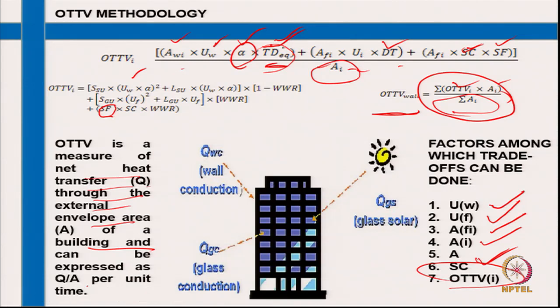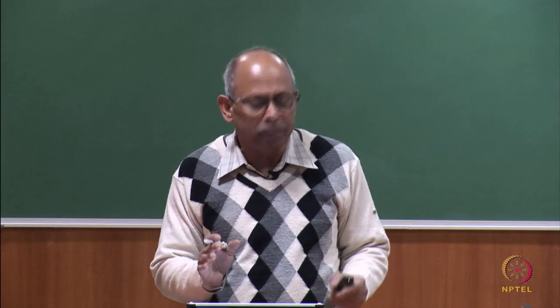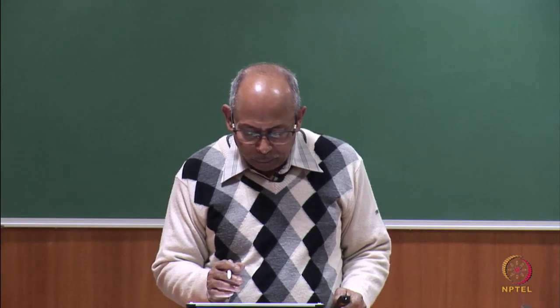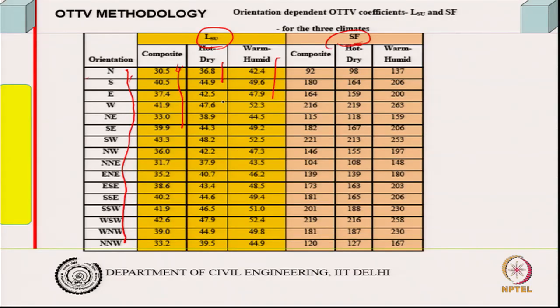These values are actually obtained through regression analysis for a large number of walls and roofs for each climatic condition, and the prescribed values in the table come from there, for example LSU values and the shading factor and so on. So linear coefficients for composite climate for different orientations are given. These values can be adopted; in the case of the Hong Kong code, they have given a linear variation, but if one looks at the regression analysis, one might find something of this kind.